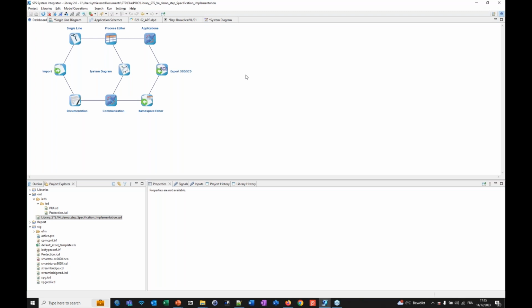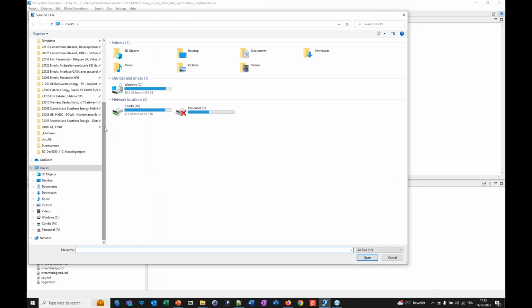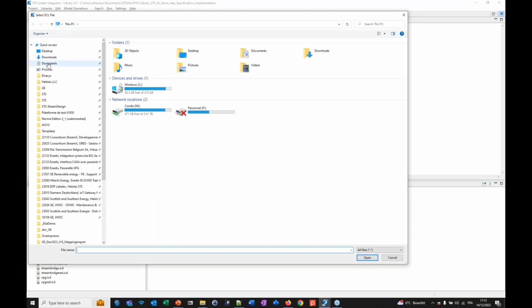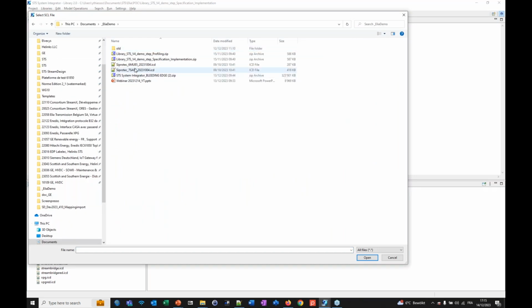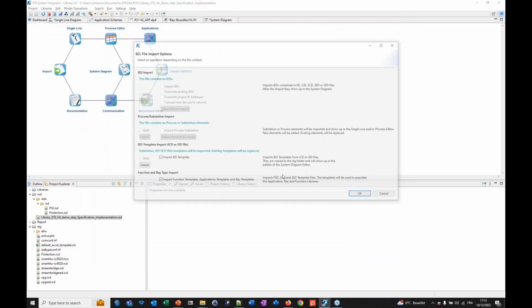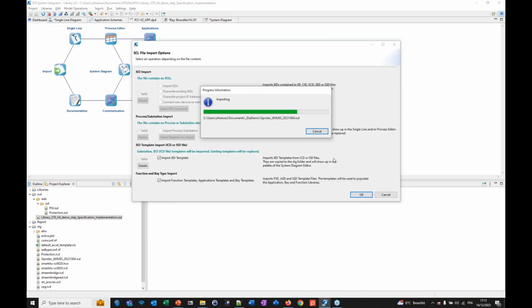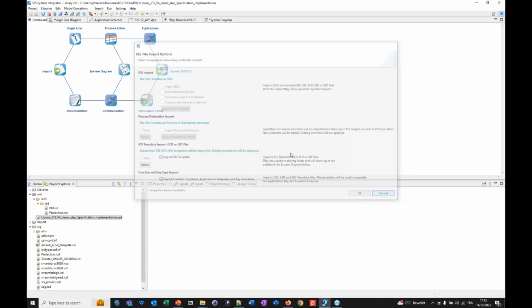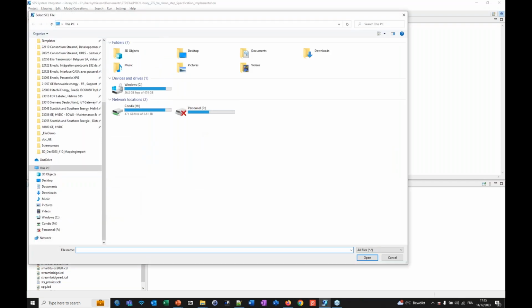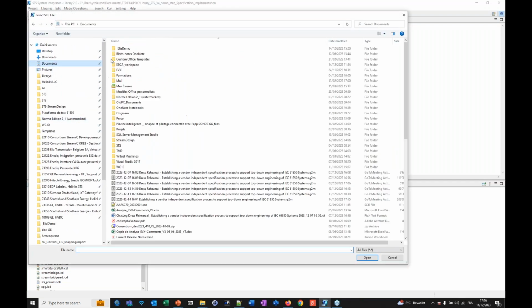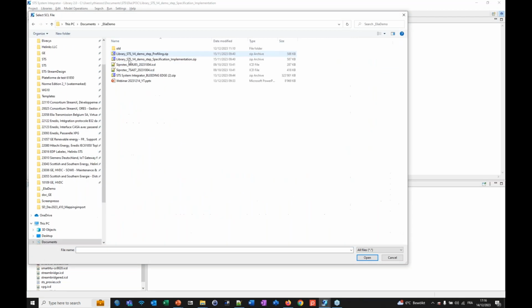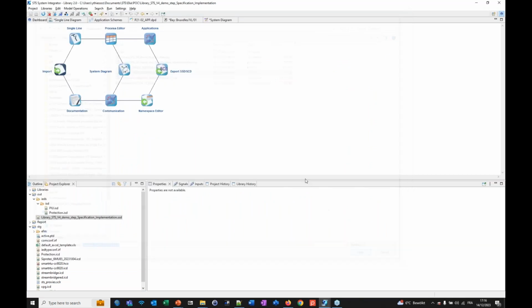The first step is to import the process ICD file. I go to the import button here, and I have received my two process ICD files from Siemens. One is for the merging unit, the PIU, and one is for the protection. I will import the merging unit, and I will import the second one, the protection.